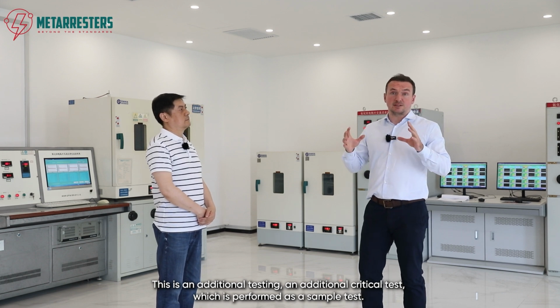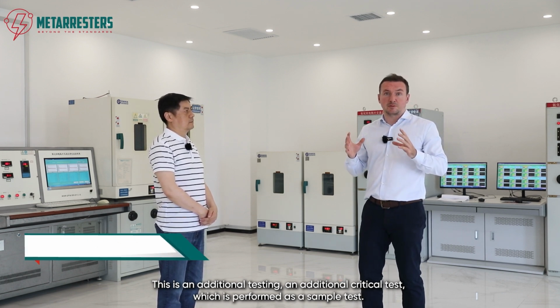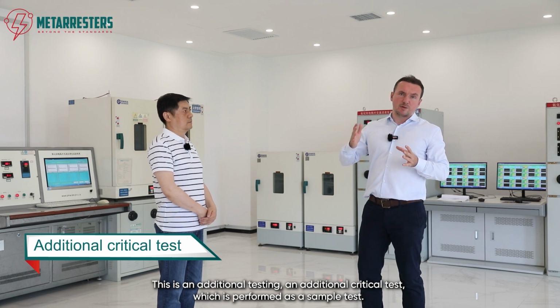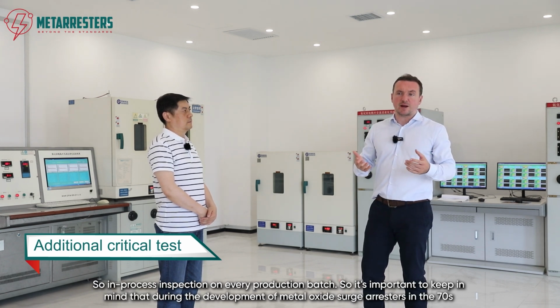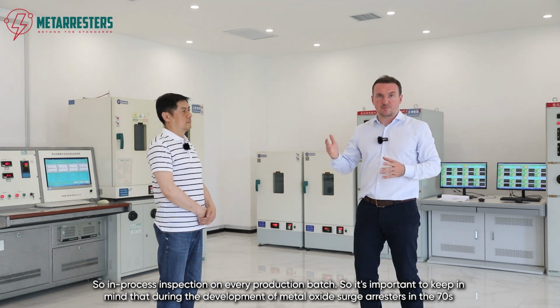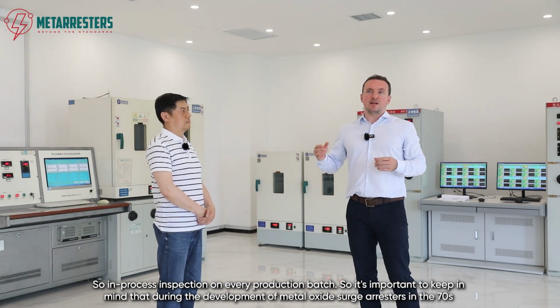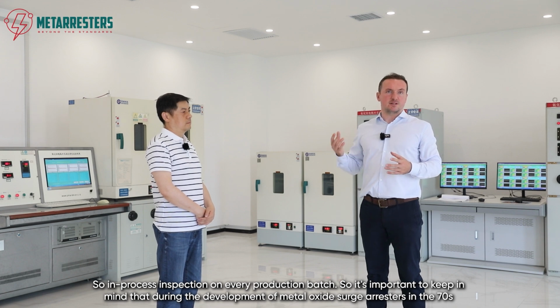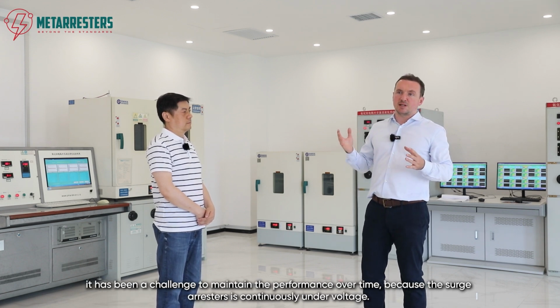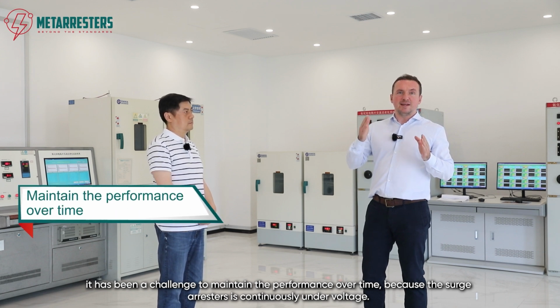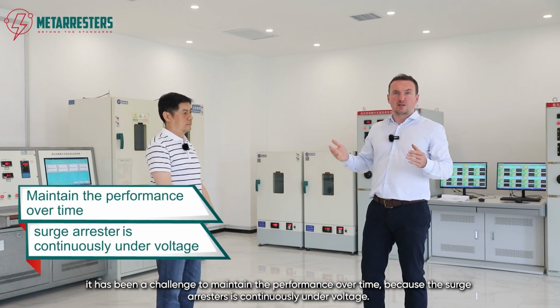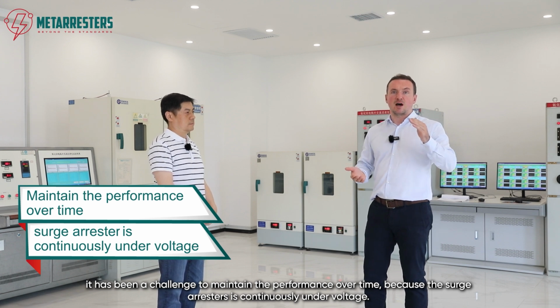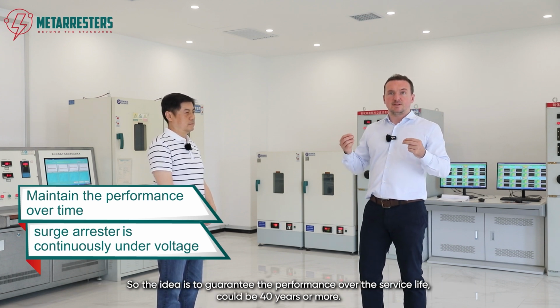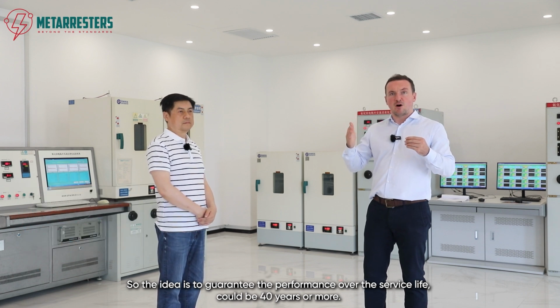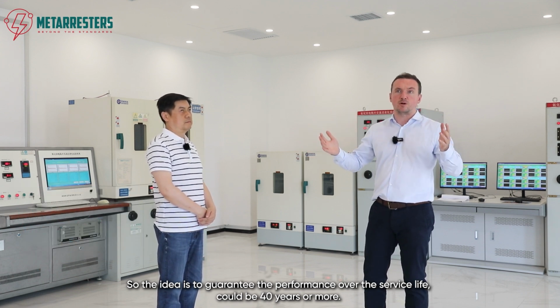So we are here in the aging laboratories. This is an additional critical test, which is performed as a sample test, so in-process inspection on every production batch. So it's important to keep in mind that during the development of metal oxide surge arresters in the 70s, it has been a challenge to maintain the performance over time because the surge arrester is continuously under voltage. So the idea is to guarantee the performance over the service life, which would be 40 years or more.